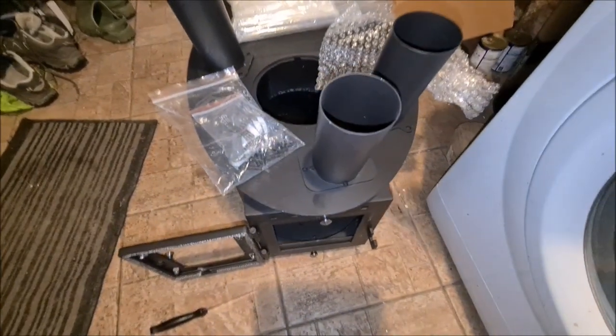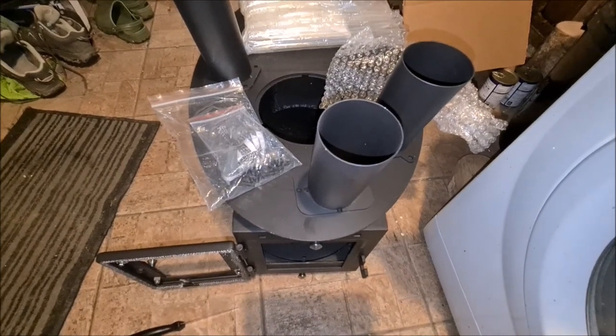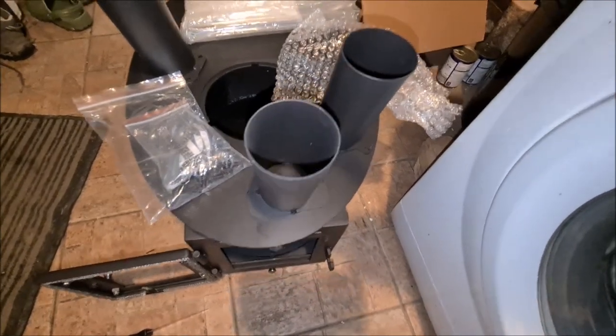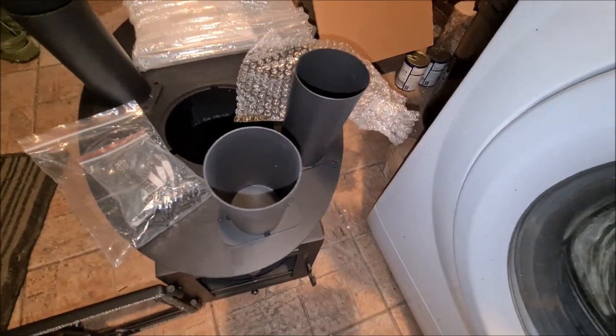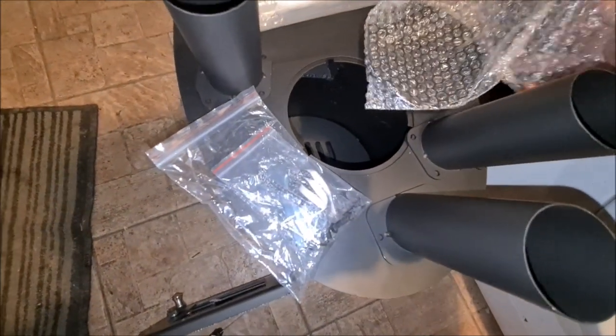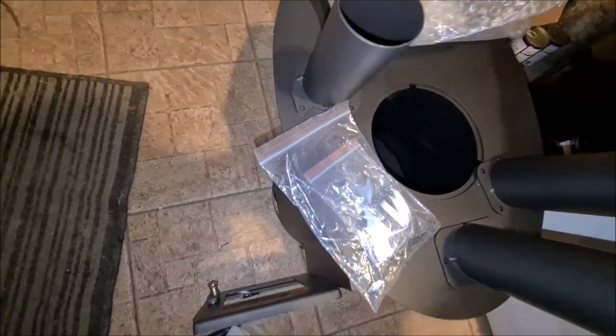I've got to disconnect the gas because we've got an old gas fire there. I can cap that up using a 15 mil pressure coupling blank. I already checked that out with my gas engineer, the place I work at, and he says, yes, you can do that. You don't need any permission for that. Just test it with some soapy water, make sure it doesn't bubble. He says you should be fine. Have I done it before? Yes, many a time. This is the lid. So I'll show you me disconnecting the gas and doing all that.